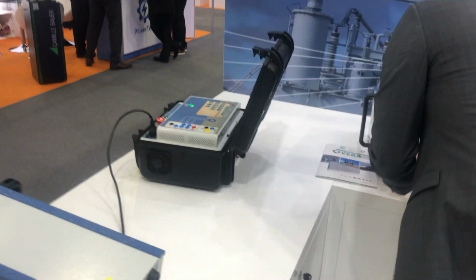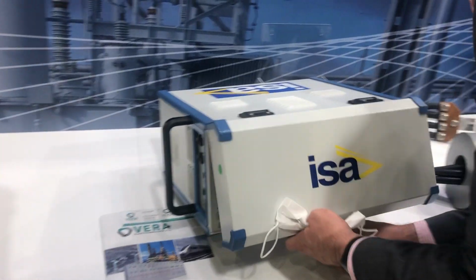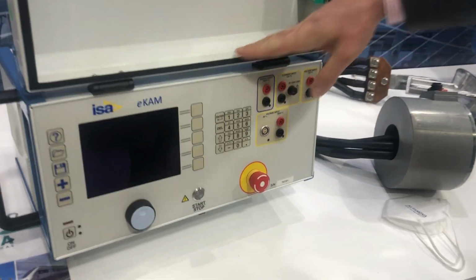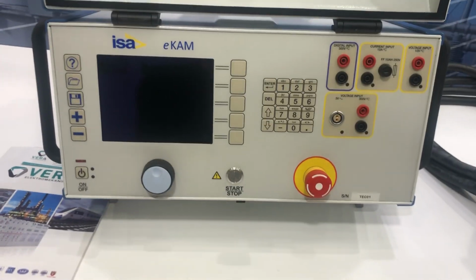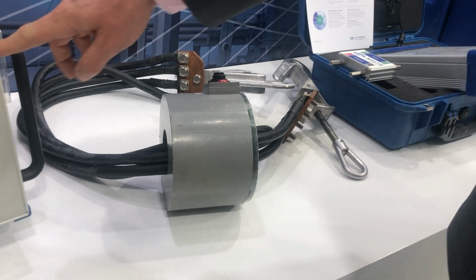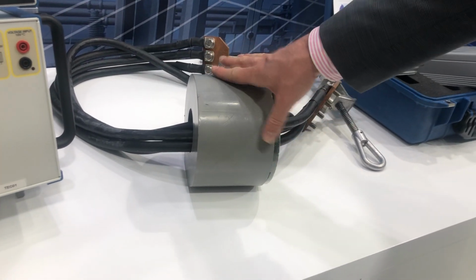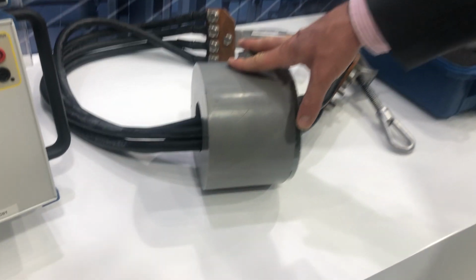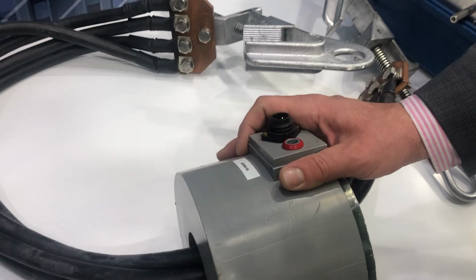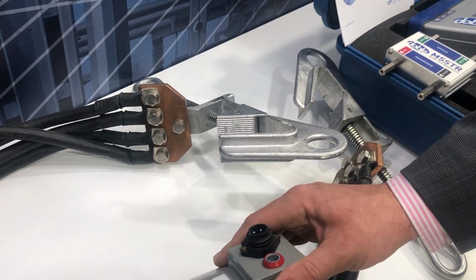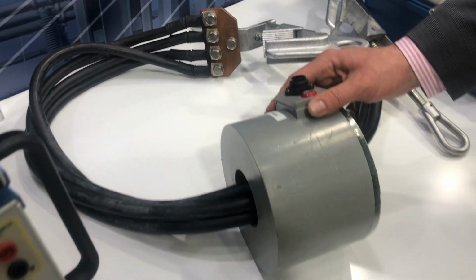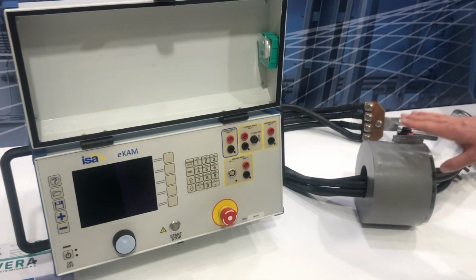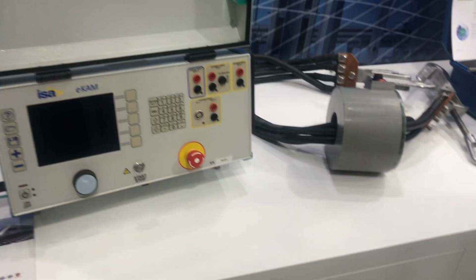Here we have eKAM, which is a primary injection. If you use this guy here, you connect a 20-meter cable from here to here, and you can generate up to 2, 3, or 5,000 amps using this BUX 3000. In this case, you can generate a maximum of 3,000. So 20 meters can be surmounted with this connection.